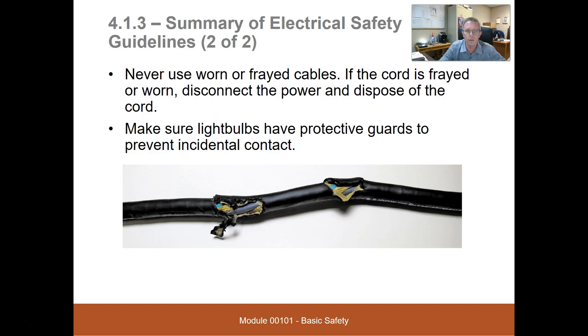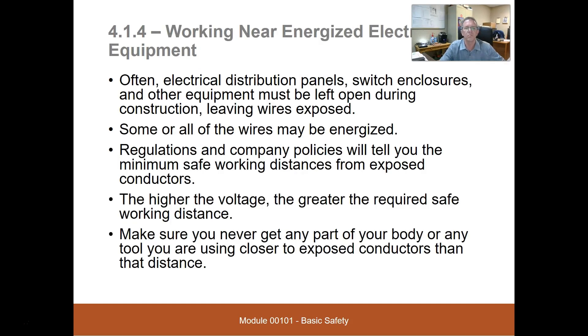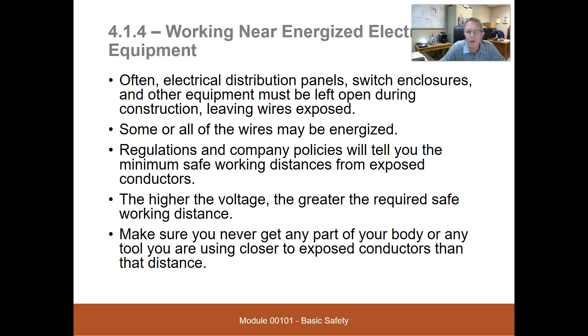Never use worn or frayed cables. If the cord is frayed or worn, disconnect the power and dispose of the cord. Make sure light bulbs have protective guards to prevent incidental contact. Often, electrical distribution panels and enclosures must be left open during construction, leaving wires exposed. Regulations and company policies will give you the minimum safe working distance from exposed conductors — the higher the voltage, the greater the required working distance.